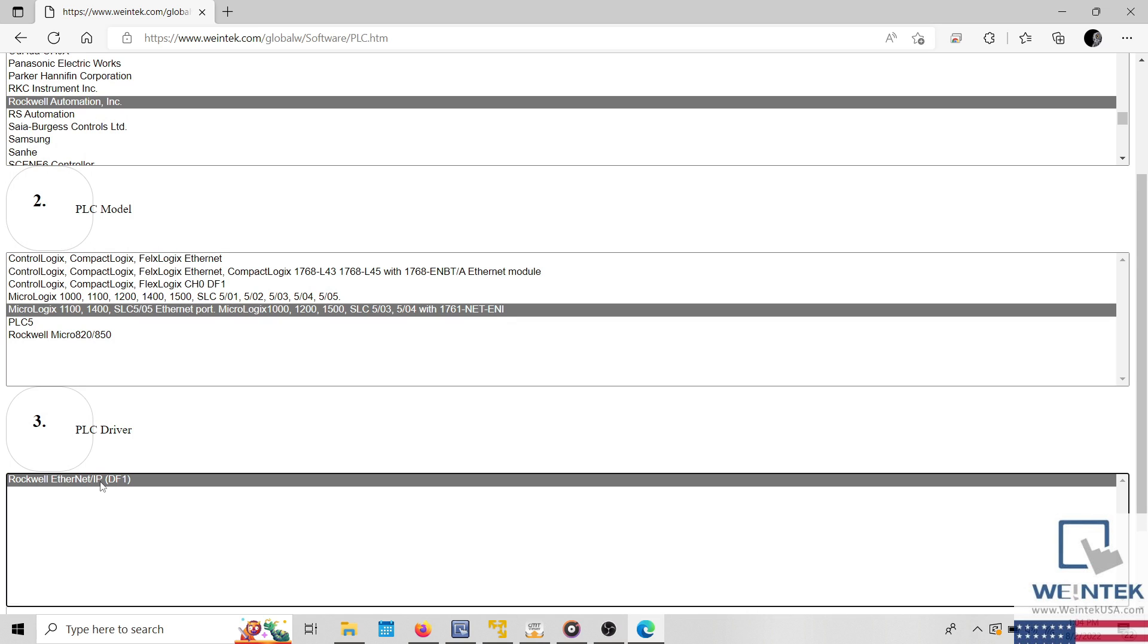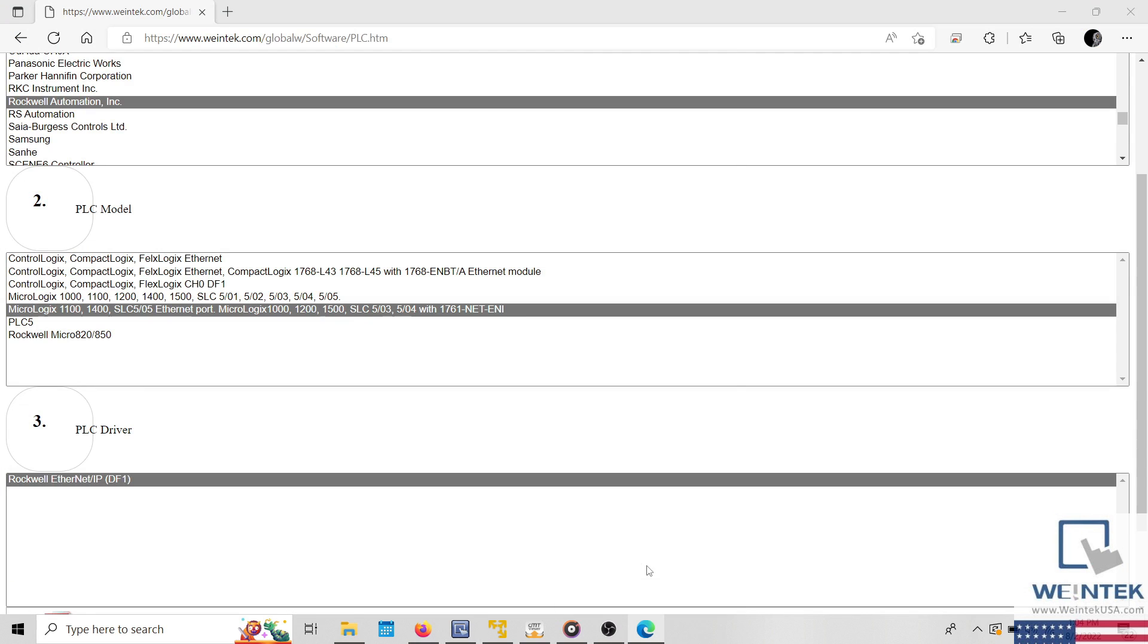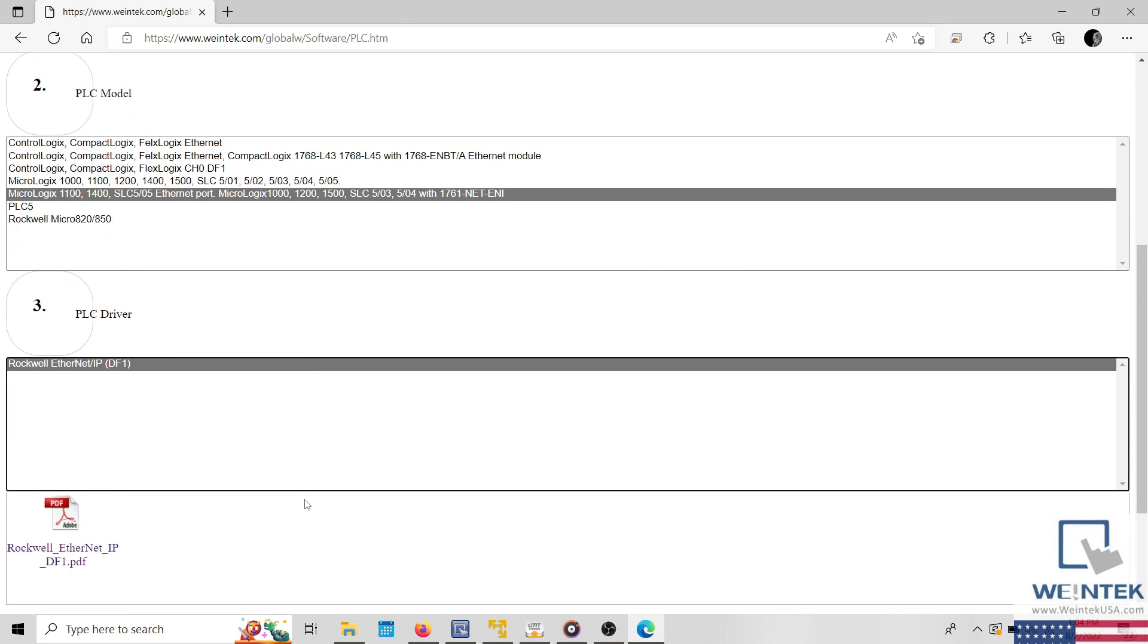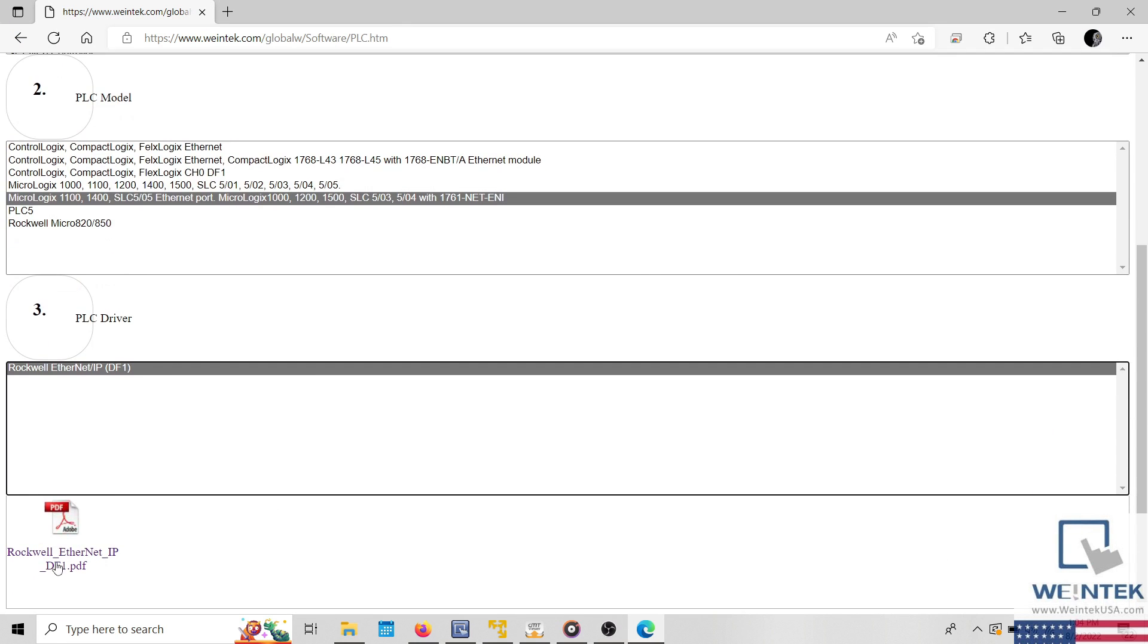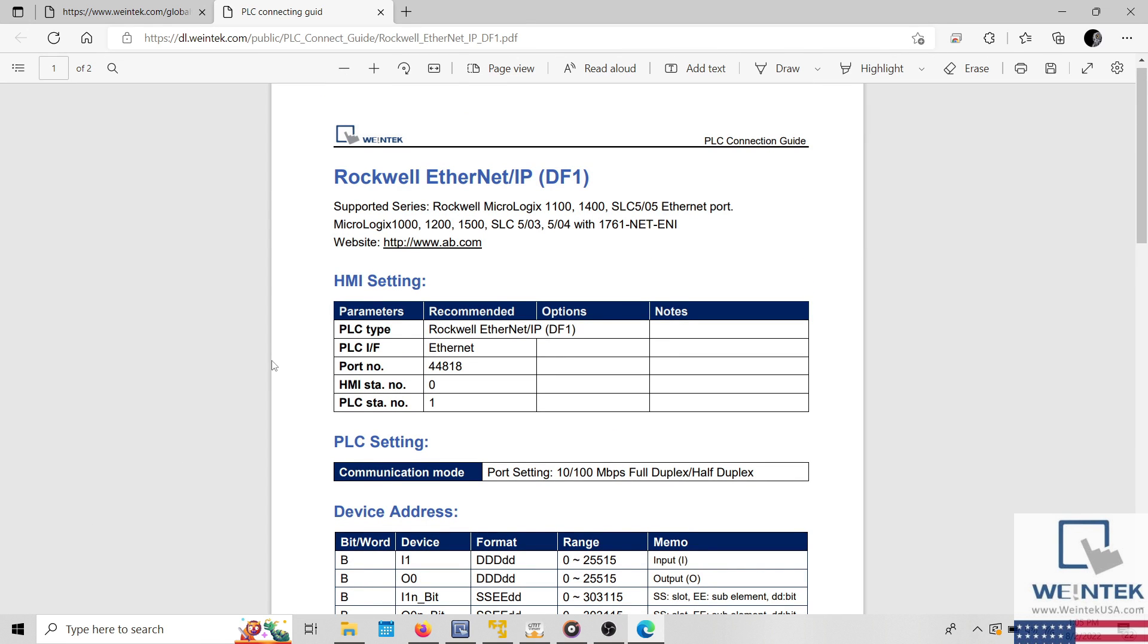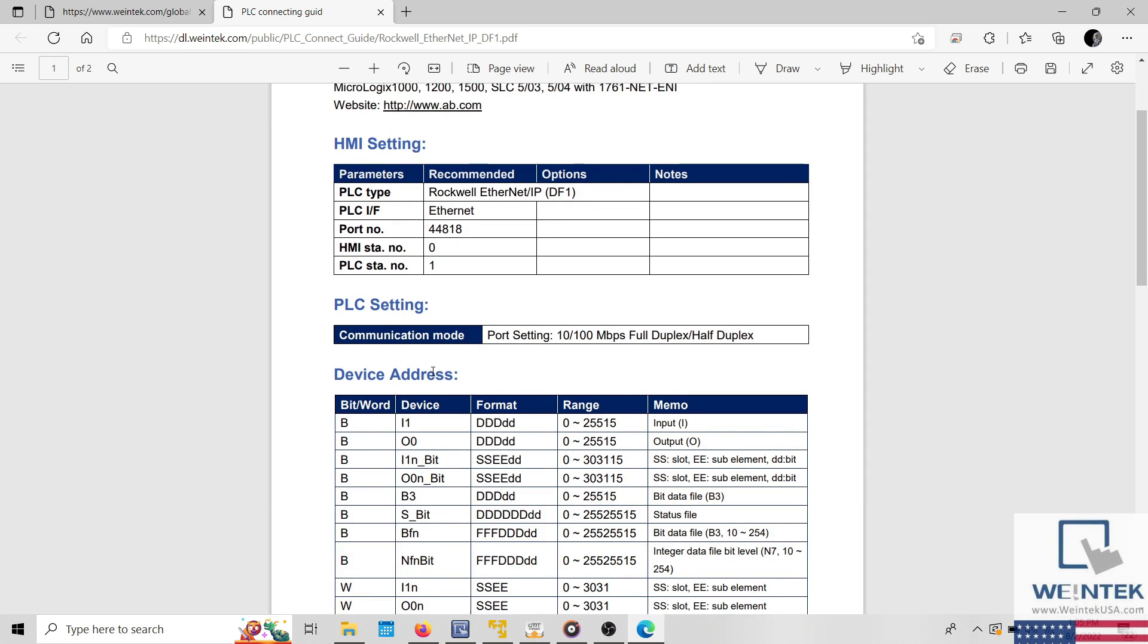Within our application, I'm using the Rockwell Ethernet IP DF1 driver. I'll select this driver within the dialog and click on the PDF hyperlink shown below. The PLC connection guide will list each PLC supported by the selected driver. It also contains the recommended communication parameters, the supported addresses, information related to wiring, as well as any instructions that must be followed in order to achieve device communication.